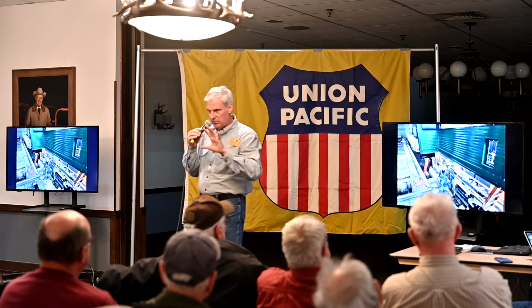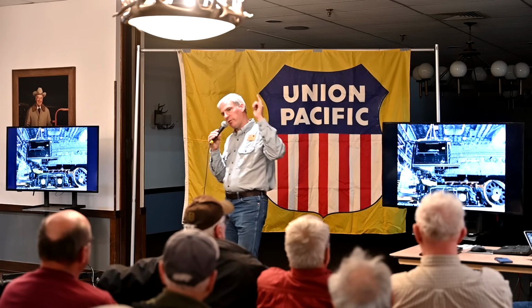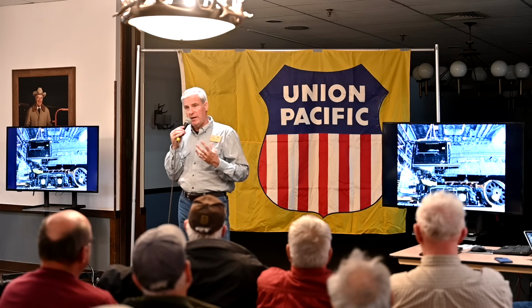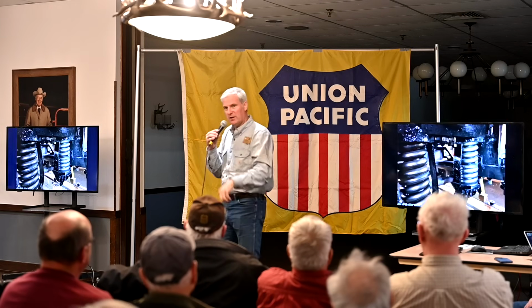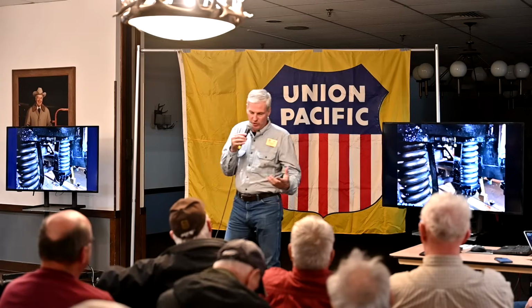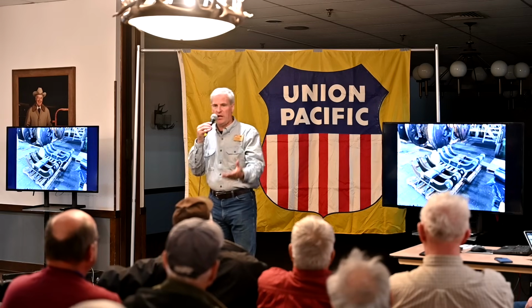And you run that through, and now you've got this giant resin bed, this tank full of these beads ready to go. Now you pump your water through it. And that water goes through, and all the calcium in that water has a strong attraction, and it's going to take the place of that sodium. Now the calcium is going to get sucked out of the water. You like my sound effects? Yes. But the sodium is released into the water. So now you get sodium, and sodium carbonate, sodium bicarbonate. And that's what drives that pH up. And that's why we blow down so much.